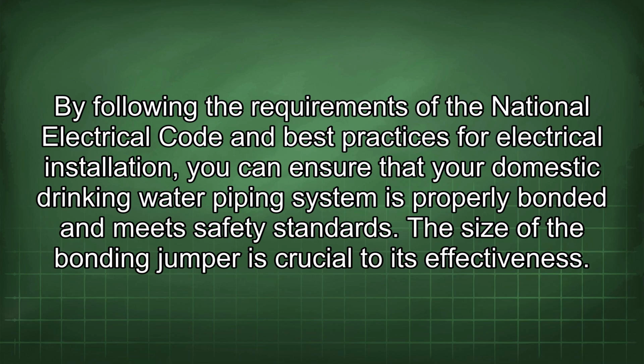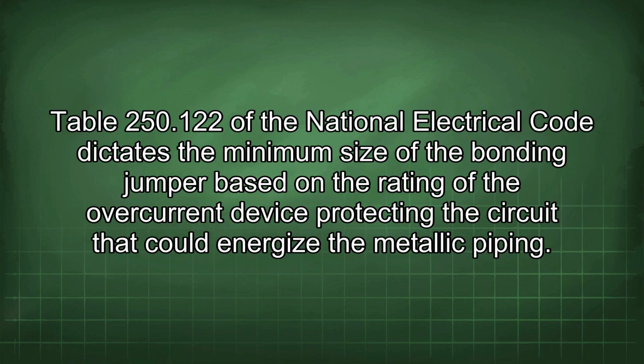The size of the bonding jumper is crucial to its effectiveness. Table 250.122 of the National Electrical Code dictates the minimum size of the bonding jumper based on the rating of the overcurrent device protecting the circuit that could energize the metallic piping.